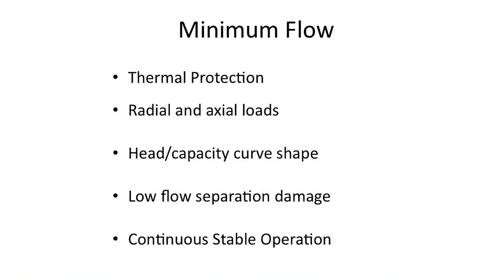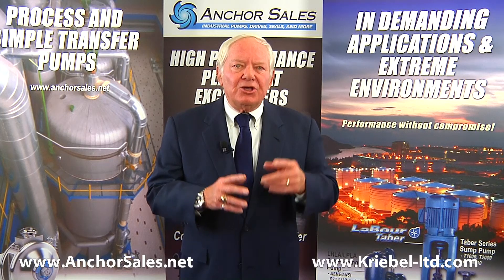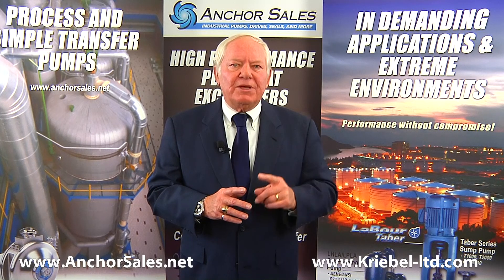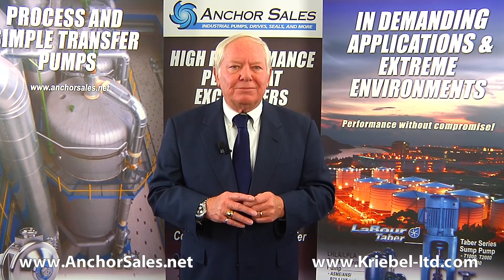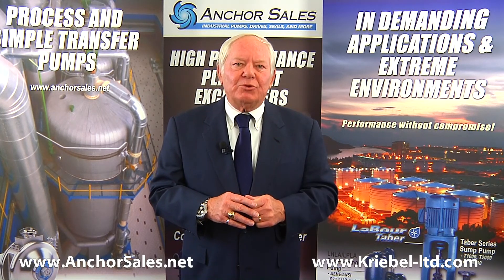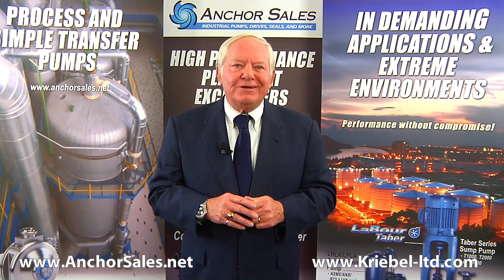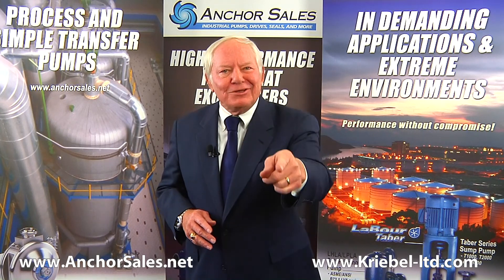In summary, your pump needs protection from overheating, excessive axial and radial loads, and from unstable operation from either curve shape, low flow recirculation, or suction specific speed. Your pump supplier can tell you what the minimum flow requirements are for your specific pump. We know this information will be useful to you, but if you need help, we're here for you. Thank you.